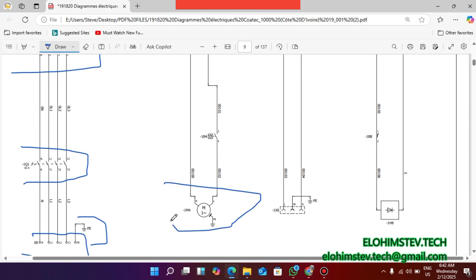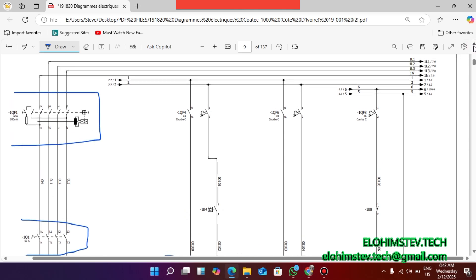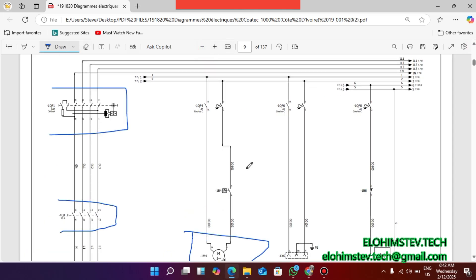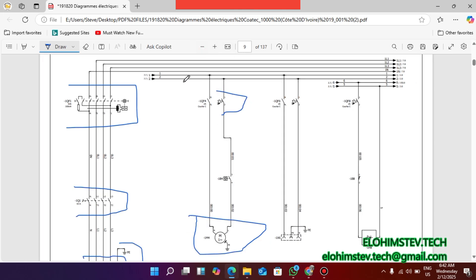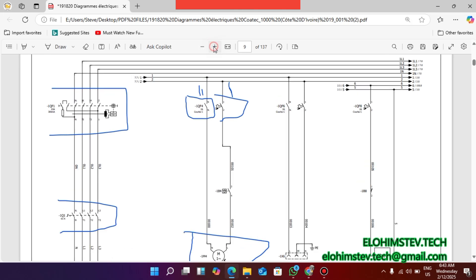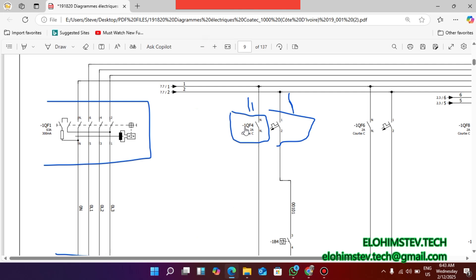Before this motor can work, let's check the components that need to be closed before it can work. We have this circuit breaker here and this motor takes line and neutral. If you read it you see it has a neutral line, a neutral line, and this is the power line. Also this is a contact which needs to be closed. To find this contact you need to check the number - it is QF.